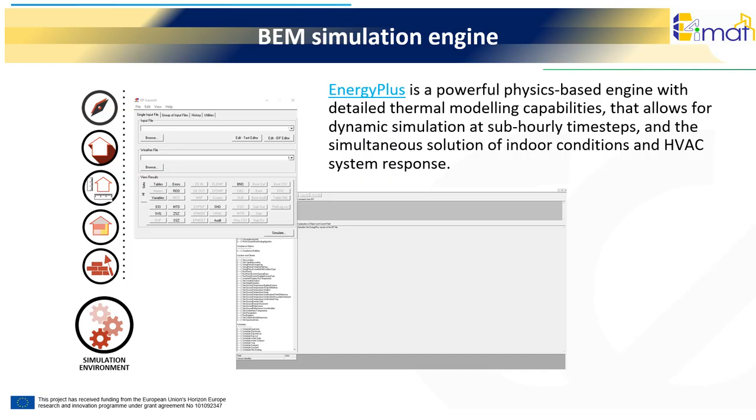Finally, EnergyPlus, a whole building energy simulation engine developed by the U.S. Department of Energy. It is a free, open-source, and cross-platform simulation engine that is capable of modeling the heating, cooling, lighting, ventilation, and other energy flows in buildings. EnergyPlus is a powerful physics-based engine with detailed thermal modeling that allows for dynamic simulation at sub-hourly time steps and for the simultaneous solution of indoor conditions and HVAC system response.